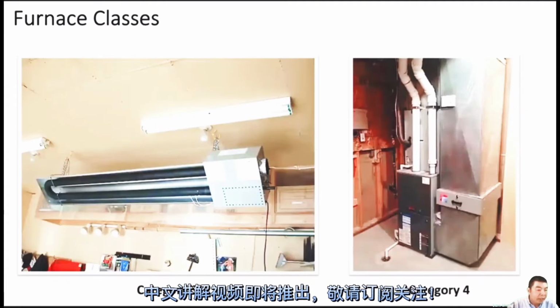Okay, thank you. For category 3, in fact, normally it's just for garage heaters. That's what I saw. I haven't seen a category 3 furnace, but most of the time it's a garage heater like this. Category 3 has a flue loss of less than 17%. The gas code definition for category 3 is flue loss less than 17%, and inside the exhaust pipe is positive pressure. That means the pressure inside the pipe is higher than outside.